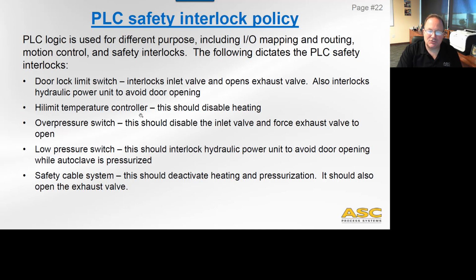We have the high limit temperature controller. This should be disabling heat. Overpressure switch, this should disable inlet valve and force the exhaust valve to open. Low pressure switch, this should interlock the hydraulic power unit to avoid door opening. And the safety cable system, this should deactivate heating and pressurization. Should also open the exhaust valve. So we're going to move forward.